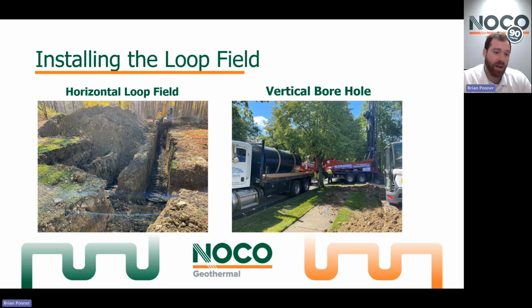Where we don't have an area that large to install these trenches and all the piping underground, we do what's called a vertical borehole. For the vertical borehole, we have a water well drilling truck come in and drill up to a 500-foot deep borehole. This borehole gets 6-inch wide steel casings put into it until we hit bedrock. Once we hit bedrock and we're drilling through bedrock, it becomes its own casing. So above bedrock, we're casing that hole with steel. And below bedrock, we're using the natural stone of the earth to be the casing and keep the rigidity and structure of that hole.